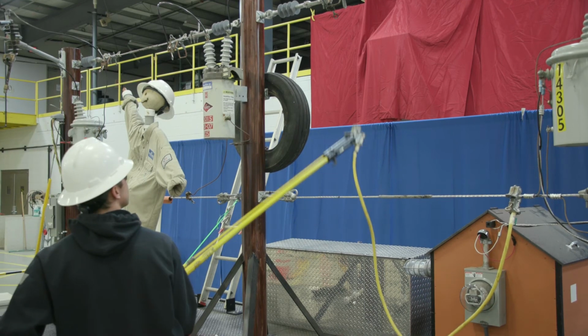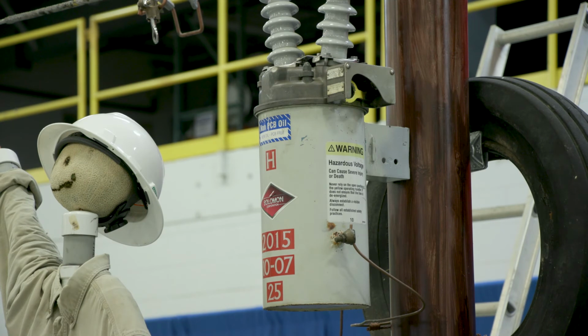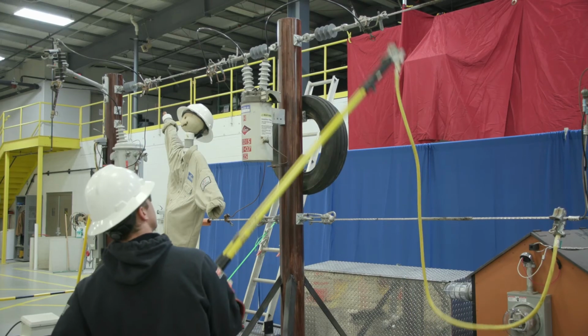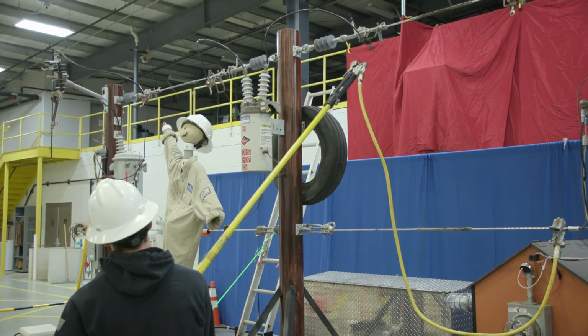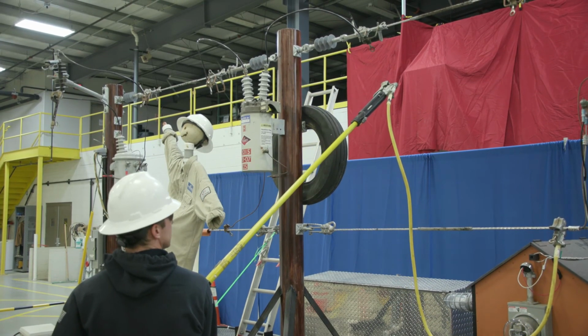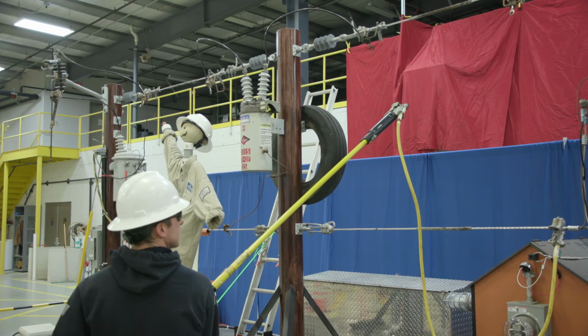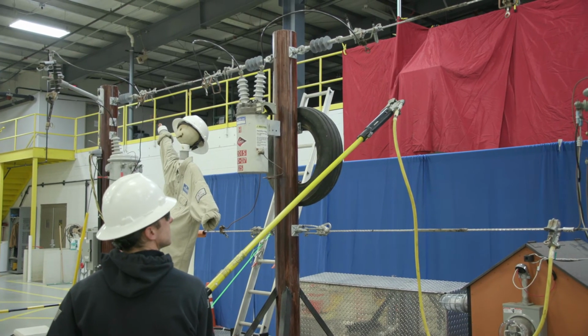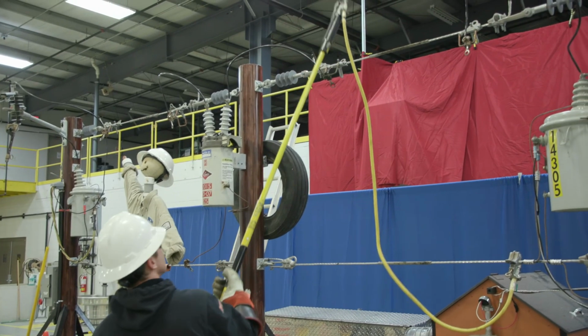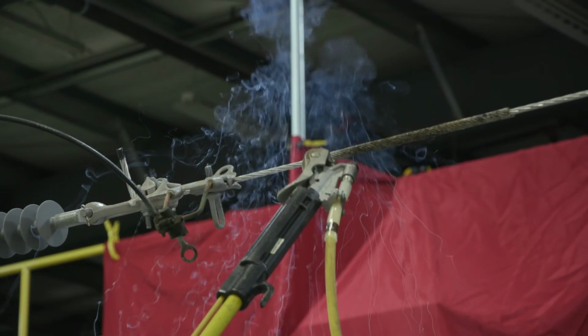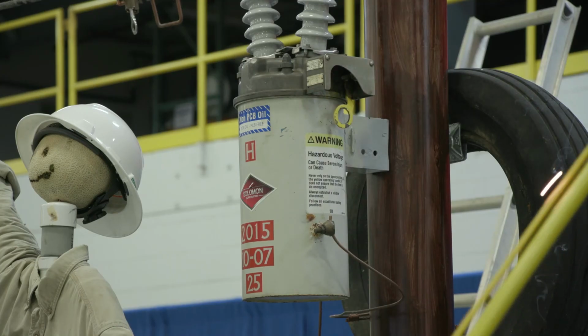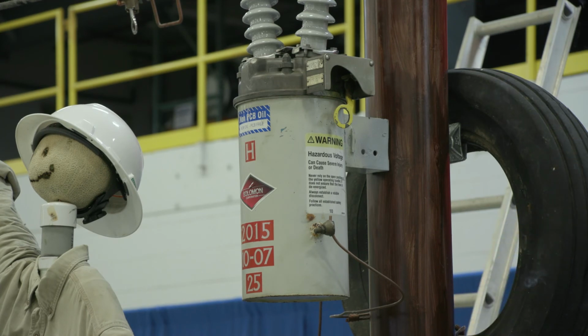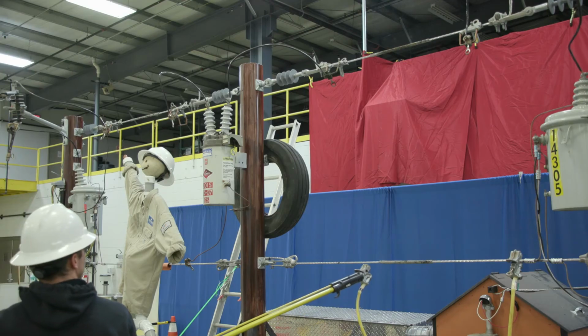The device we're going to show you right now is an oil circuit recloser. It's a semi-smart device with some intelligence. When there's a fault on the line, it operates multiple times, and in between each time it takes a break to see if the fault went away. If the fault didn't go away, on about the fourth operation it finally opens up, which it just did. That yellow handle on the side just came down into a down position.